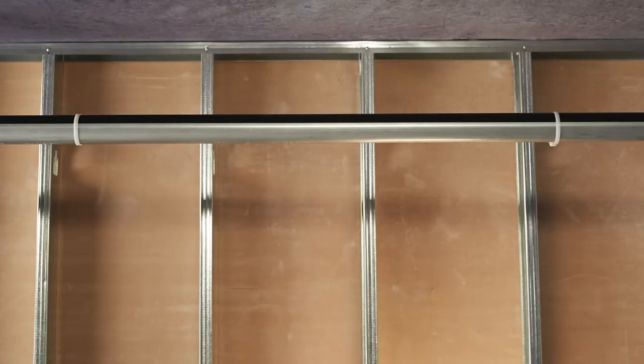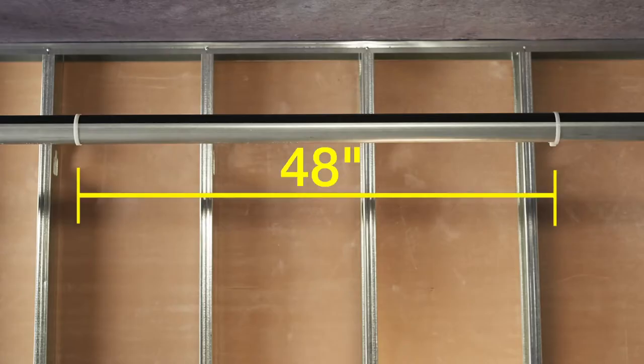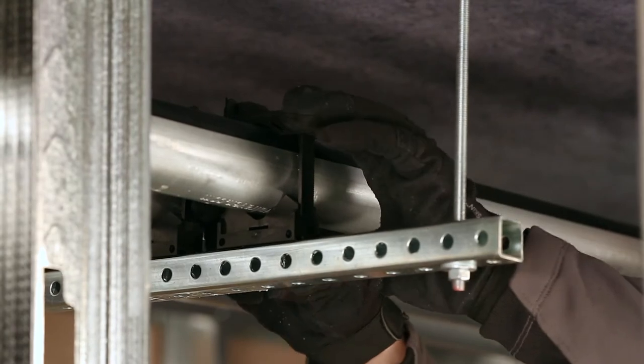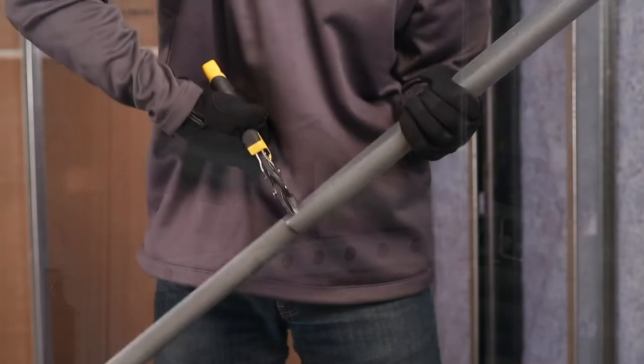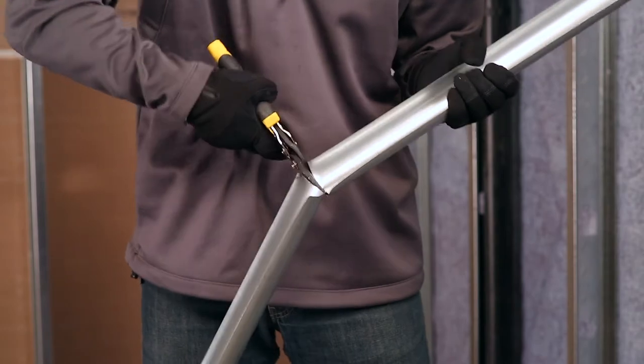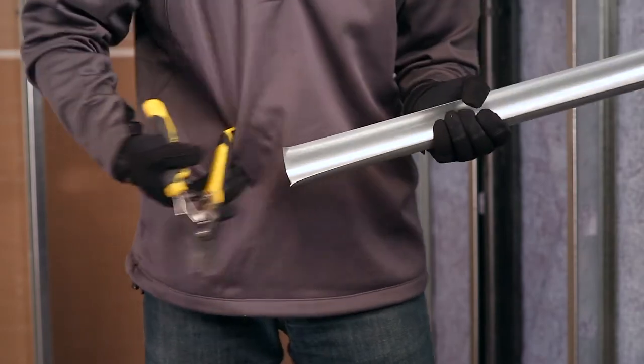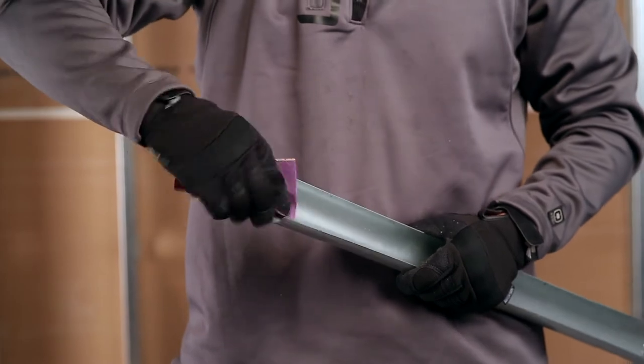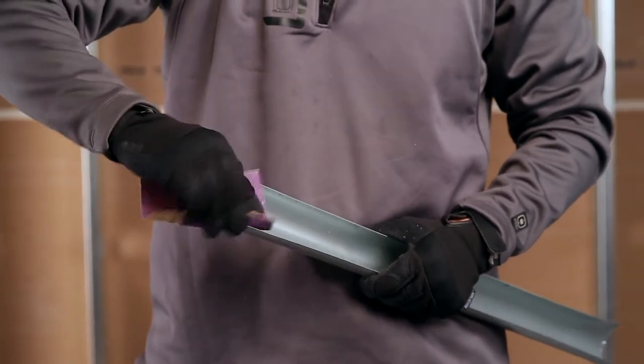Snap the tubing into the support trays. Trays should be strapped to the tubing using Viega zip ties, or equivalent, every 48 inches — two straps for trays less than 48 inches in length — for clevis and/or teardrop hangers, and only once between clamp-type hangers. When using tin snips or a reciprocating saw to trim support trays for shorter tubing runs, be sure to remove any sharp edges prior to installing trays onto the PureFlow PEX tubing.